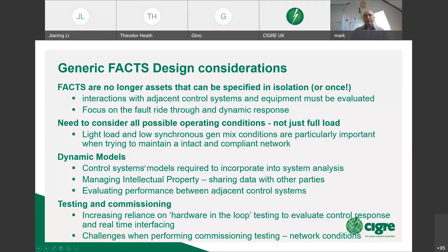And then marrying with that is how do you actually test and commission these systems? It's increasingly difficult these days to get access to the system, and you don't get long commissioning windows. More often than not, you're not getting the testing conditions you'd want either. It's very difficult to get a heavily loaded network when doing commissioning, because the last thing the control room wants is a fault that trips off a lot of capacity. So we are having to think better how we can use real-time hardware-in-the-loop testing, things like this, to minimize as much of the stage 2 commissioning work as we necessarily have to do.